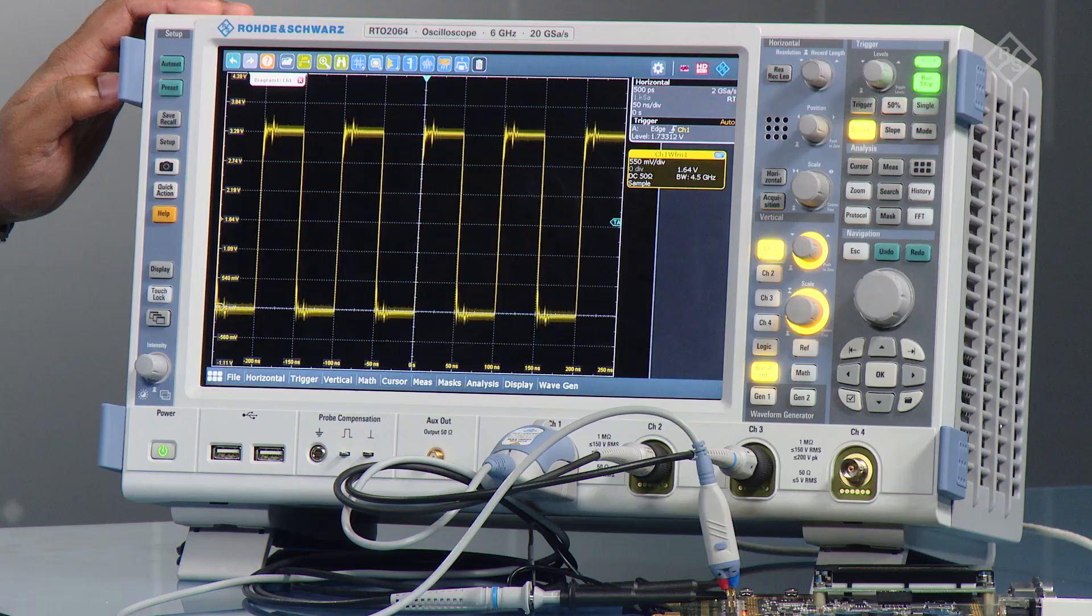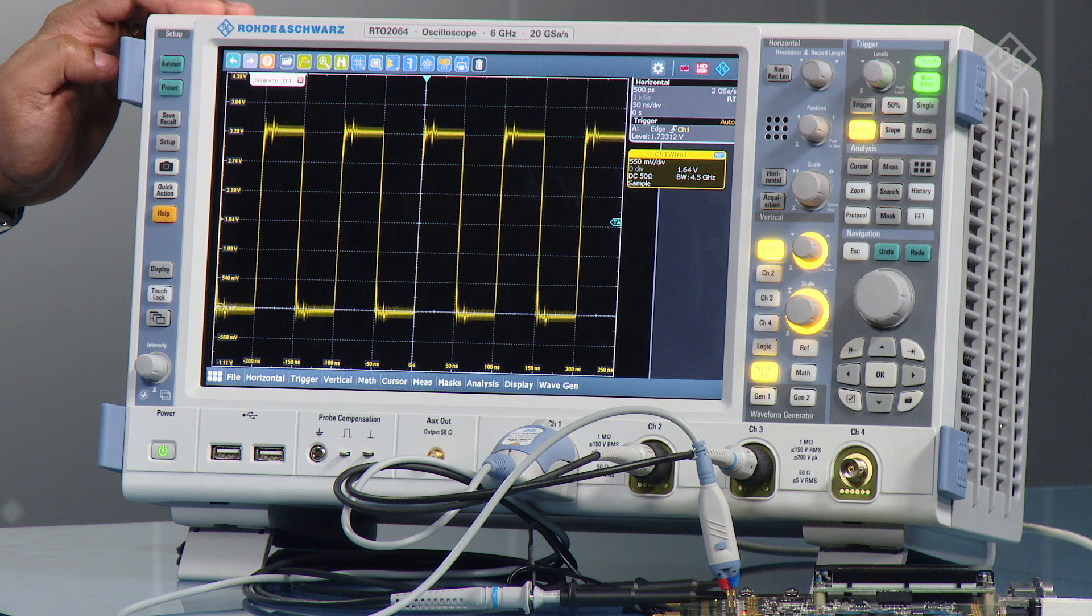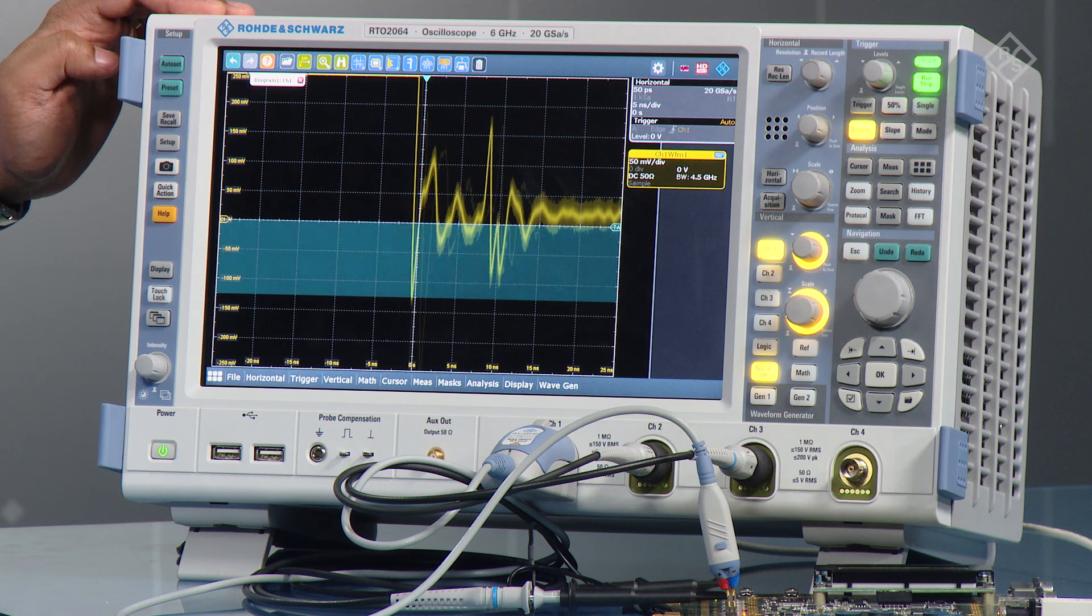As you can see I've got the RTO here, and on the left-hand side you see all the main housekeeping keys. Two of the main important keys there would be the preset key, so you can go back to a factory default state, and the magic auto-set button if you wish to use that.